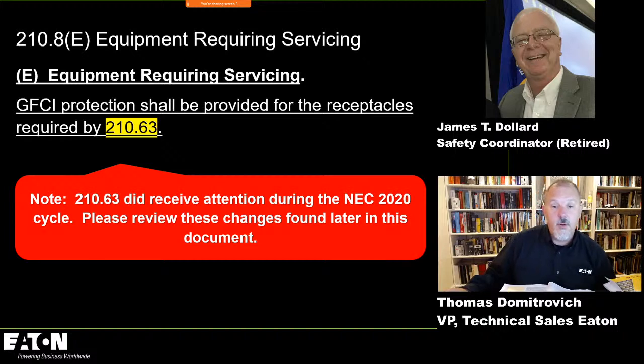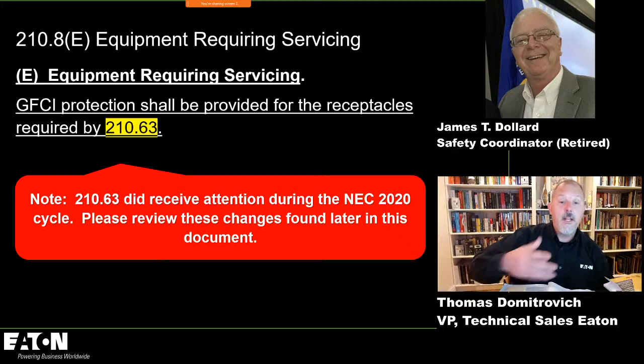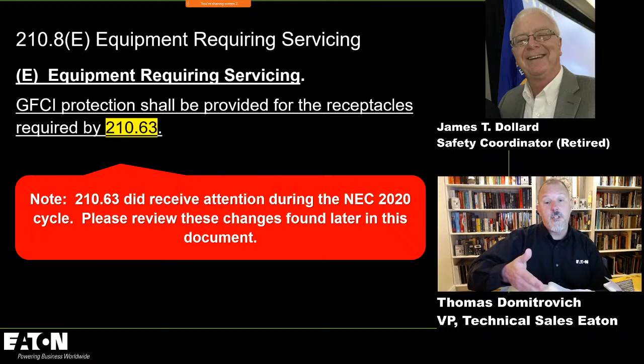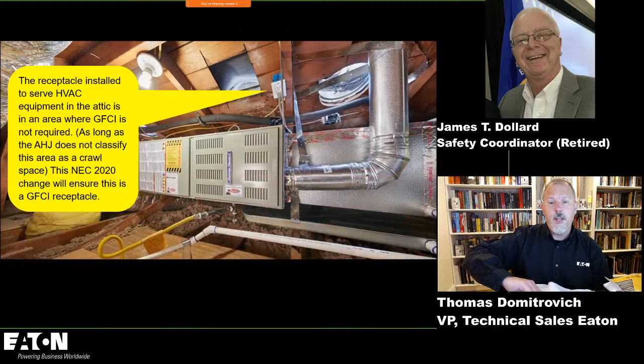210.8(E) talks about equipment requiring servicing. So 210.8 is your GFCIs, and we talked about this in the GFCI online thing that I did. We expanded this, and we made some changes in 210.63 that better organized it, and we now have a provision that if you have equipment that has a requirement based on 210.63 where you have to have a receptacle outlet there for the electrical worker to plug into, it has to be GFCI protected.